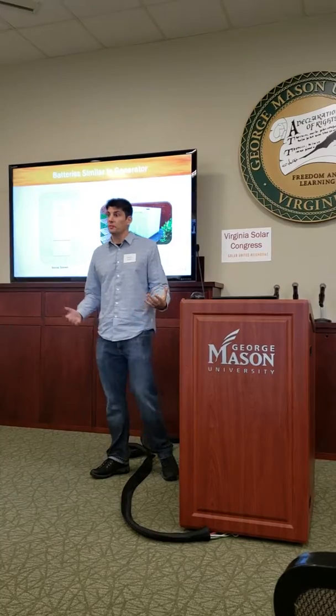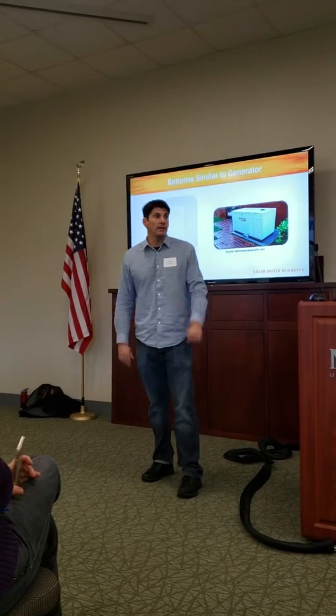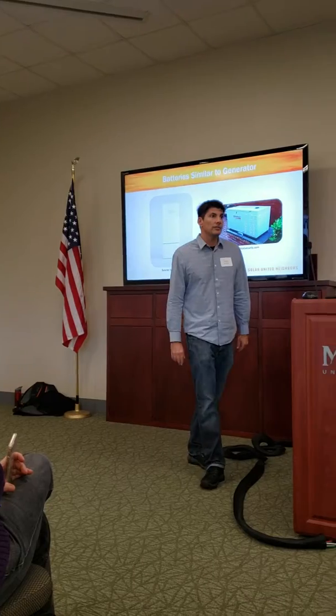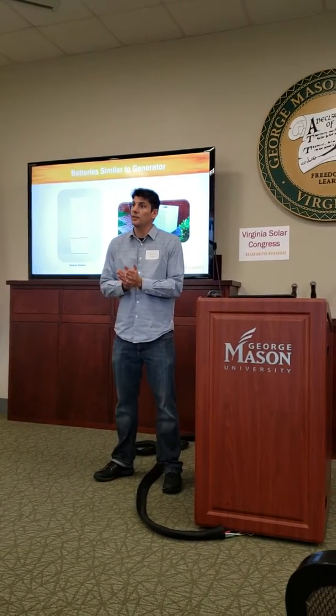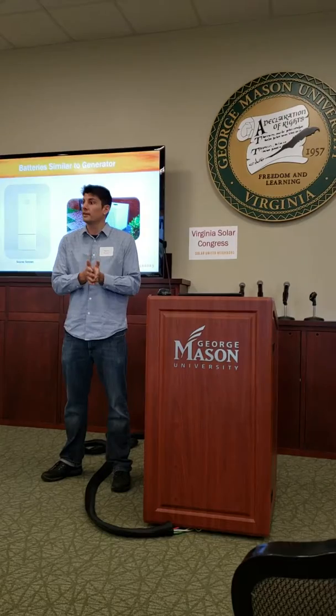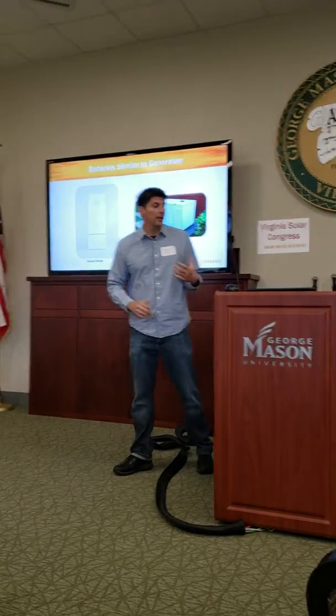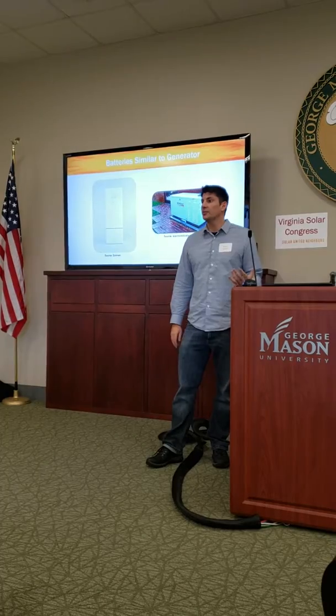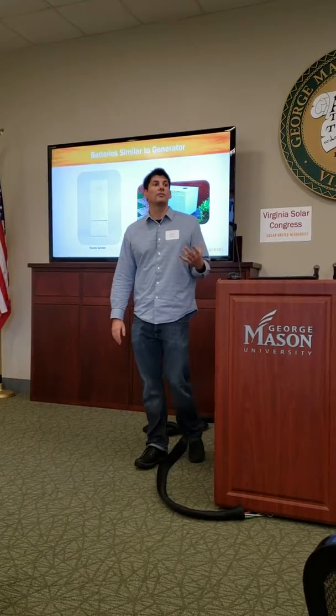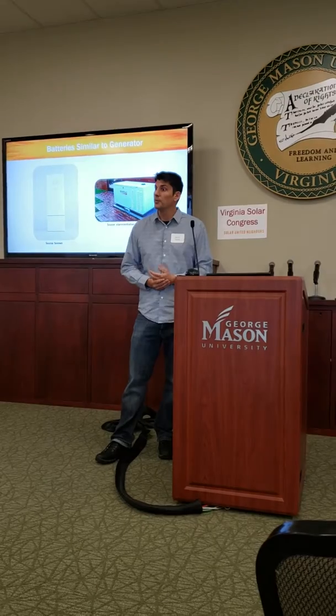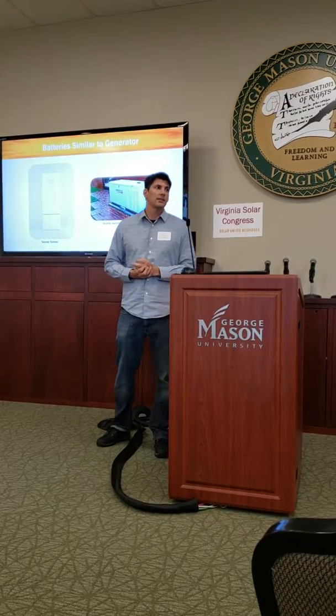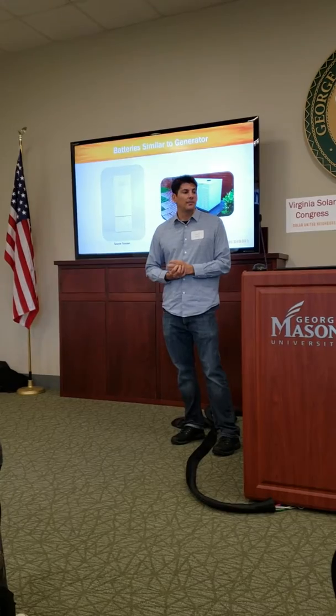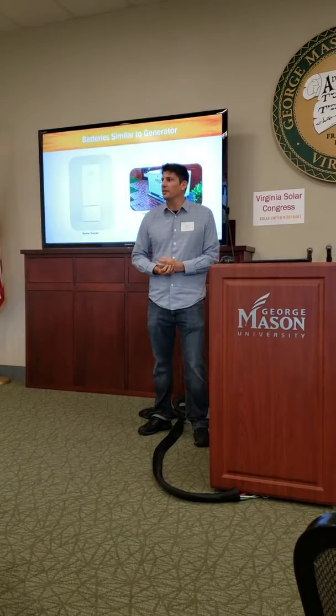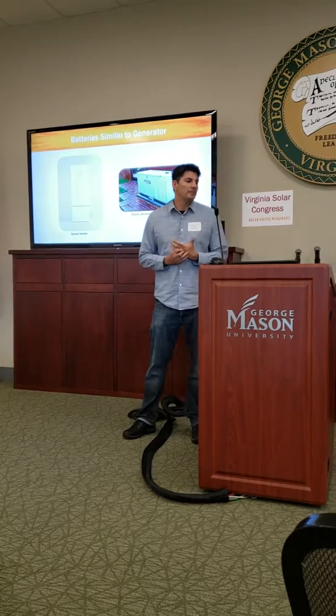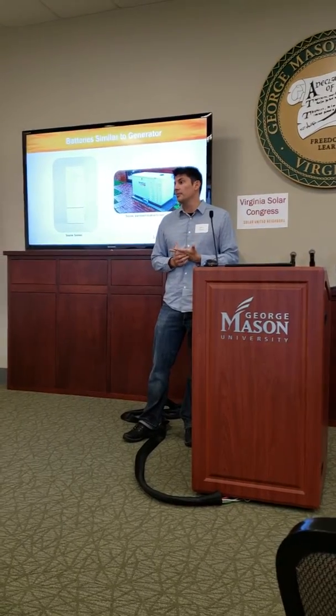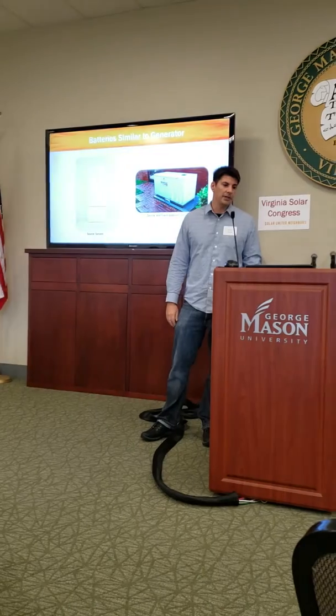Essentially they're similar to a generator. Some people might check me on this, but dollar for dollar right now, a gas generator is probably as cost effective or a little more effective than batteries. That's going to change, but the value proposition is similar. Of course, batteries don't have moving parts, don't have fuel, run a little more cleanly, so there's less noise. And the joke is, when does a generator break? When you use it, right? So that's really what the value proposition is for battery backup in Virginia.